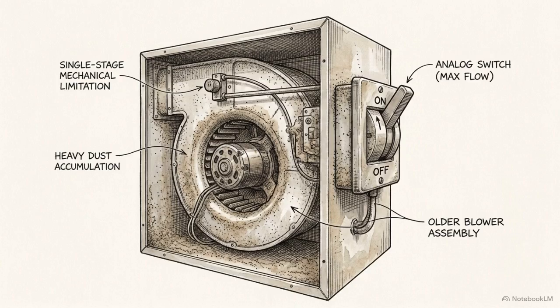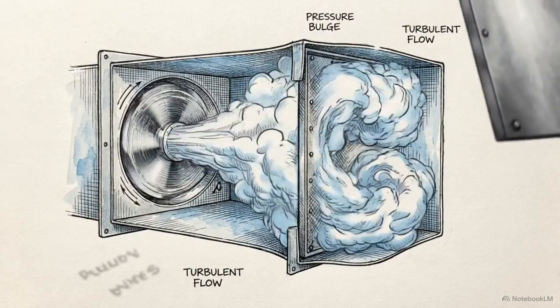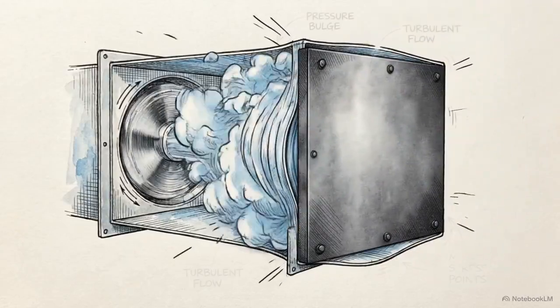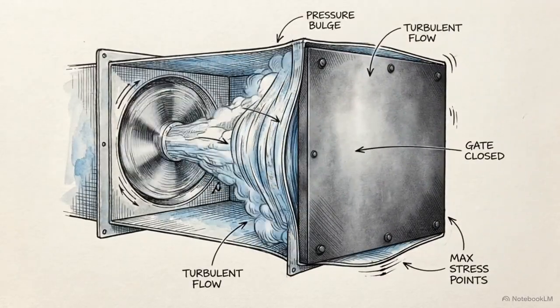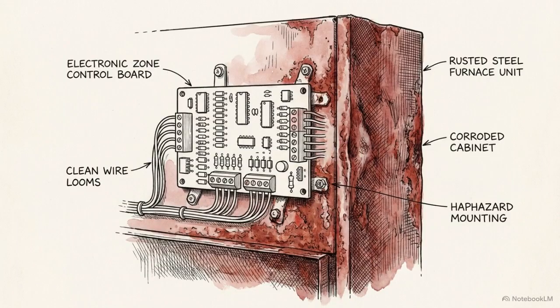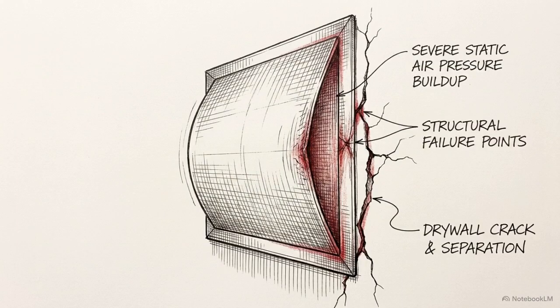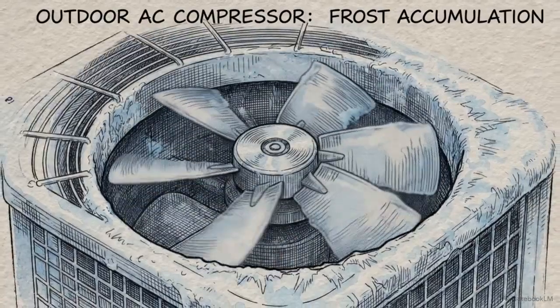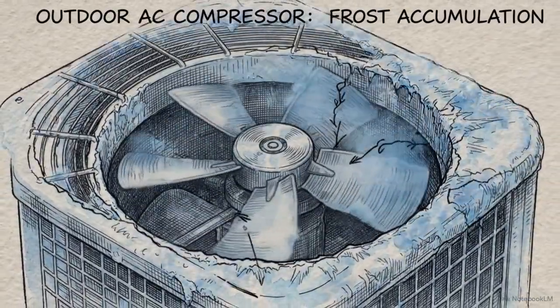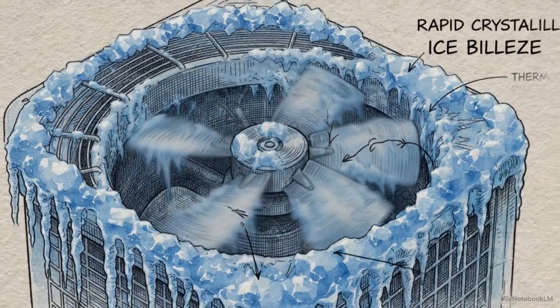Older systems usually have single-stage blowers, meaning they only run at one speed, maximum. If that blower pushes a full load of air against dampers that are closed, it creates severe static air pressure buildup inside the ducts. Grafting an advanced dual-zone setup onto an older single-stage system doesn't create efficiency. It creates excessive wind noise and guarantees your equipment will fail prematurely. Even if your indoor equipment is compatible, your system is still bound by strict thermodynamic rules that govern how and when it can be maintained.